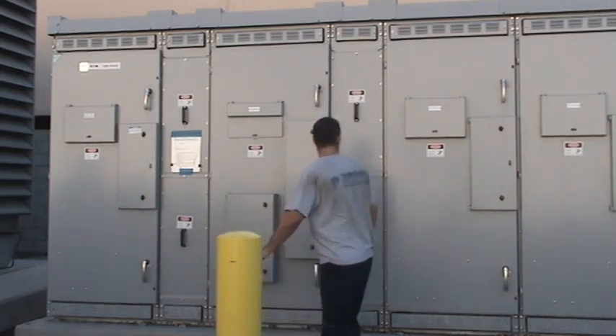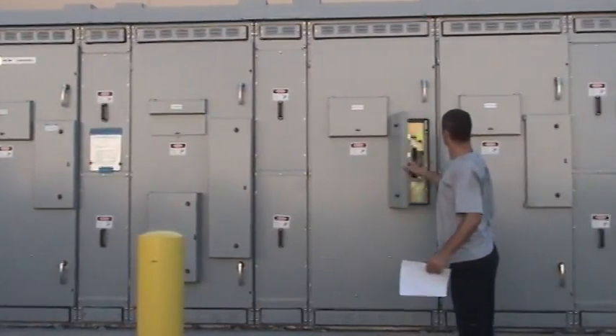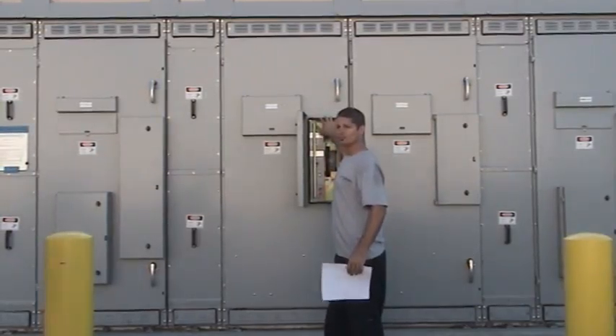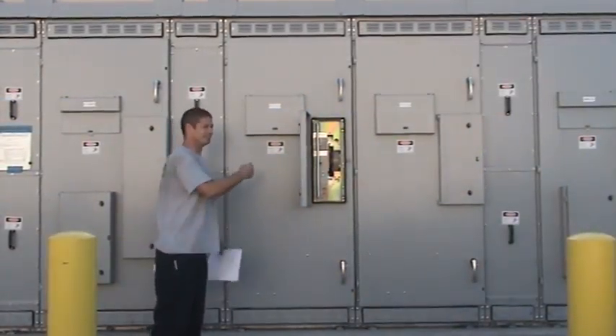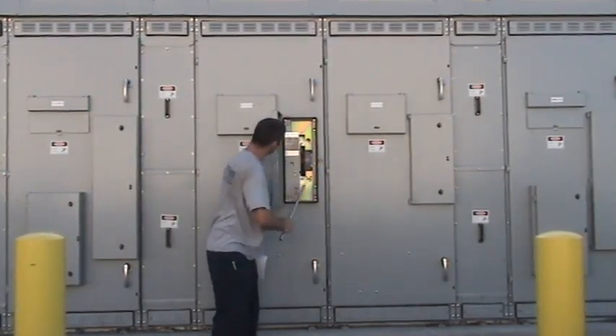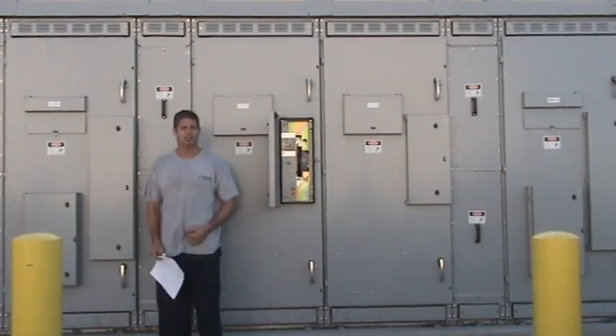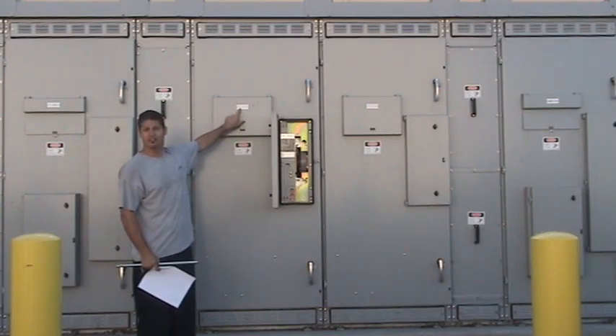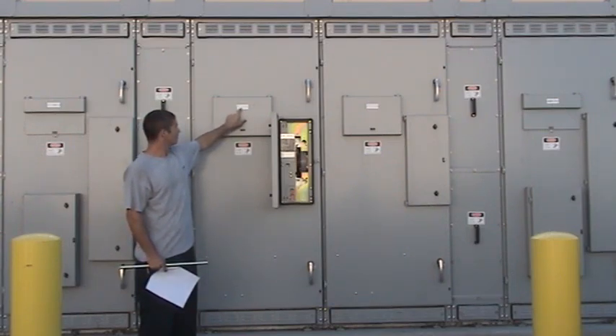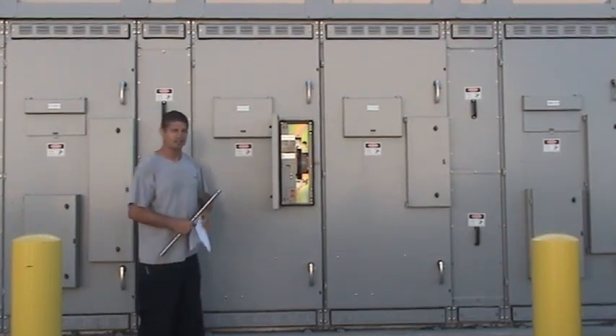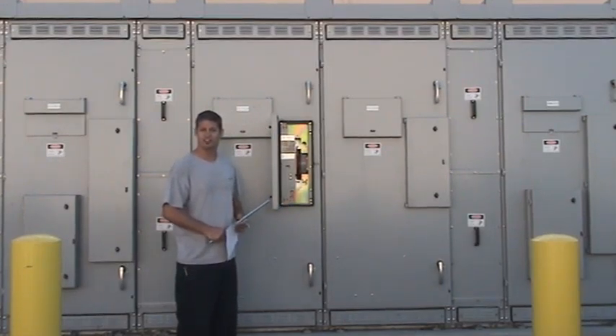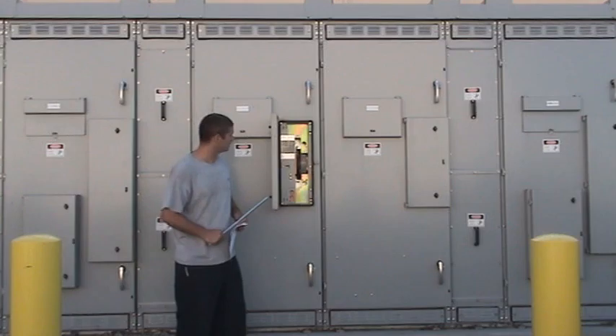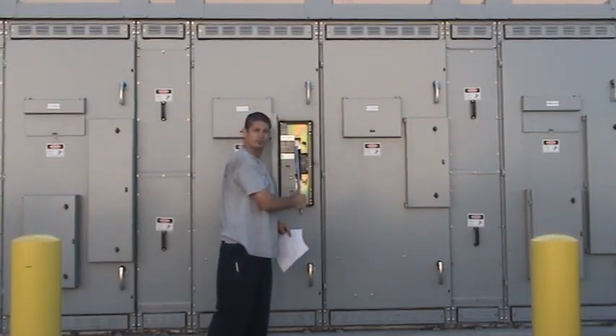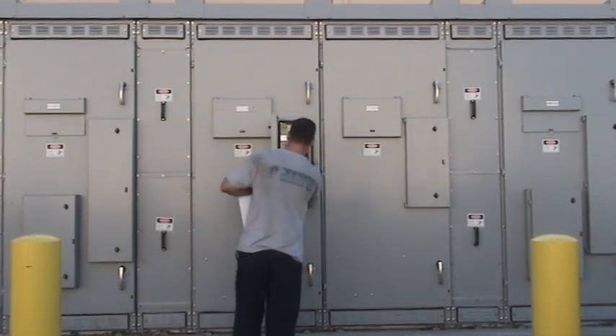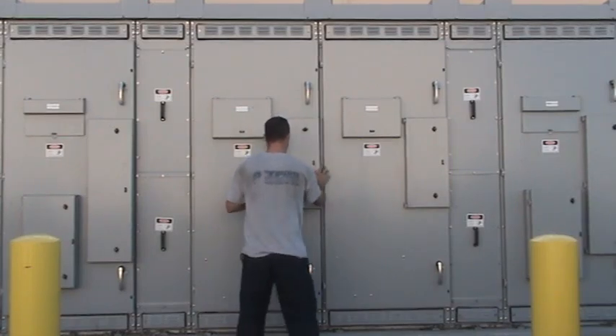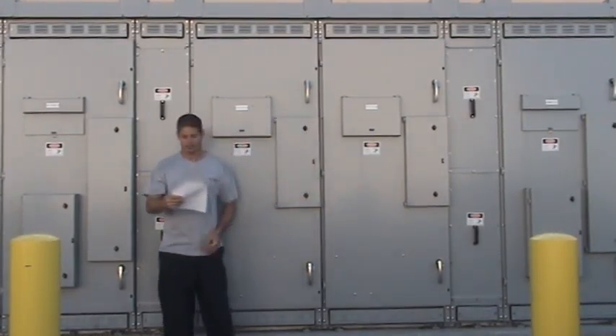Manual switches, which are these right here, control the transformers. You've got to stay behind that, but let me see from over here. These are manual switches that control the transformers on both sides of the building. So there are 4 of these total. And you can see the name tags here call out the transformer name tag, right? So this controls TX21 on that side of the building. And these are manual, and these are always in the closed position, unless there's an emergency state or something, then you would manually open them, right? They remain in the closed position at all times. And that's what it shows you on that little outline right there. The position for these in a normal state is always closed.